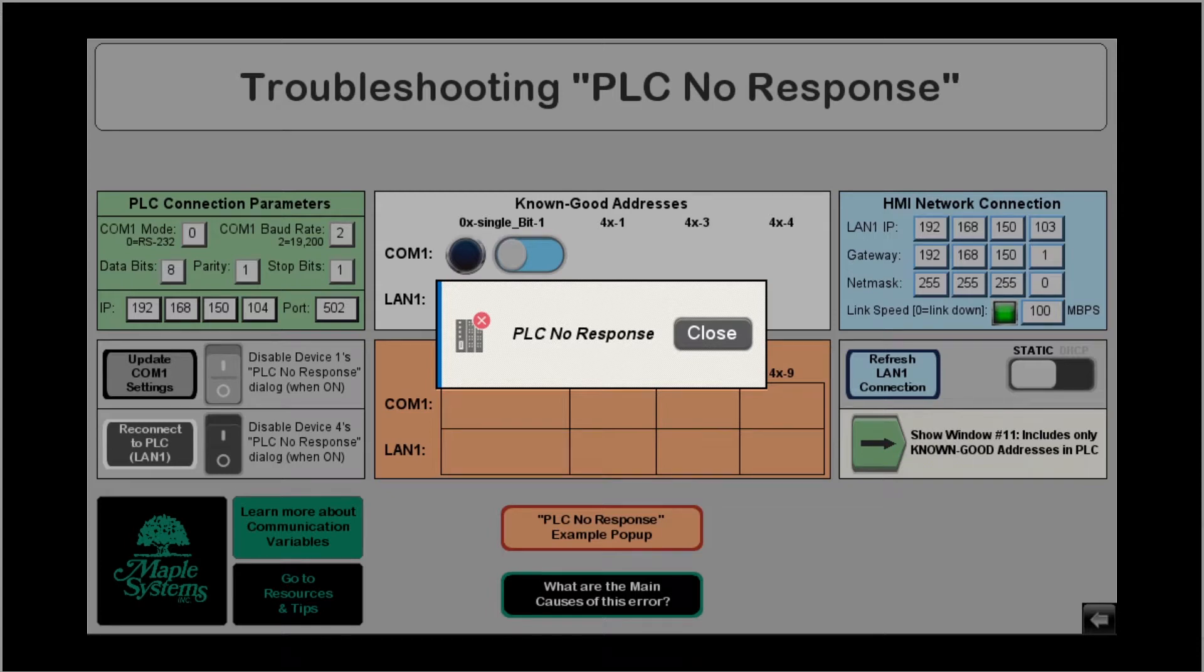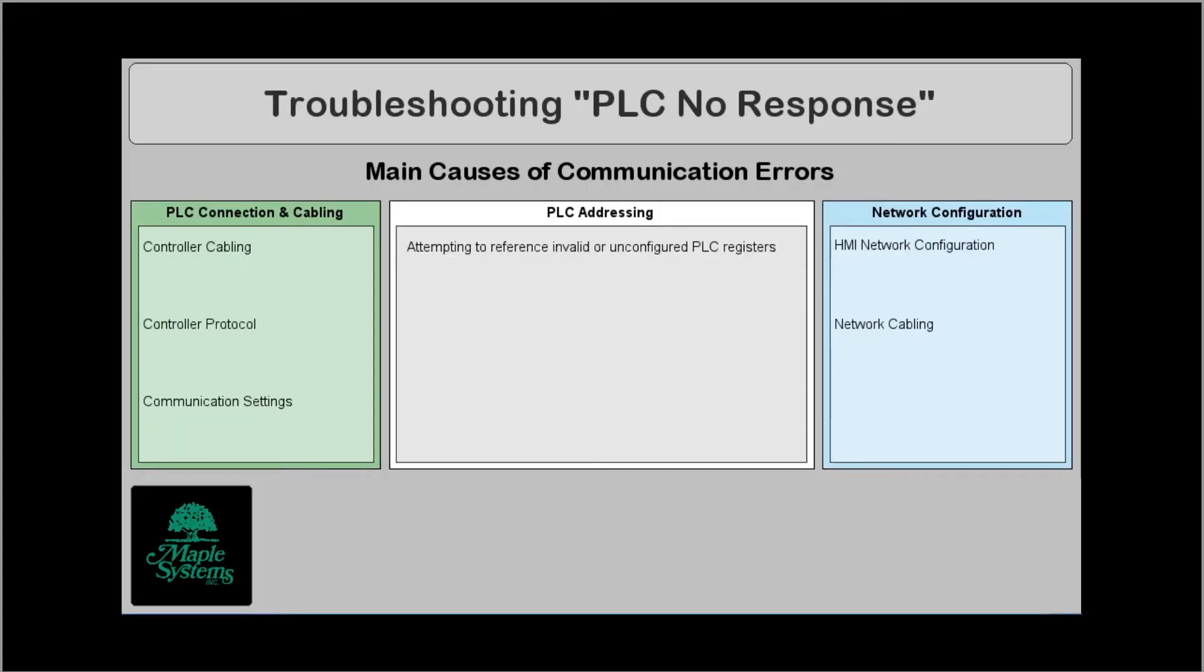Now there are a number of reasons why this can occur. These mainly relate to an issue with your cabling or your connection settings, addressing in the PLC or the network configuration that's applied to your HMI.